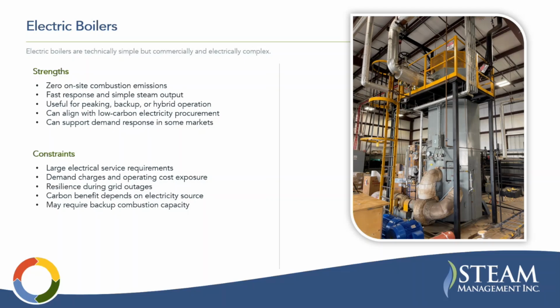So we've run numbers on some of these. Generally speaking, and obviously this depends on utility rates, it can cost around 4 times as much for the electricity to run the boiler as compared to gas for a comparable gas boiler. The carbon benefit depends on the electricity source. So if you're using electricity from a coal boiler, you're not really doing much, because generating heat in the coal boiler to generate electricity to then generate heat is more carbon emissions than burning gas directly at the boiler. And it may require backup combustion capacity anyway, which we'll talk more about.